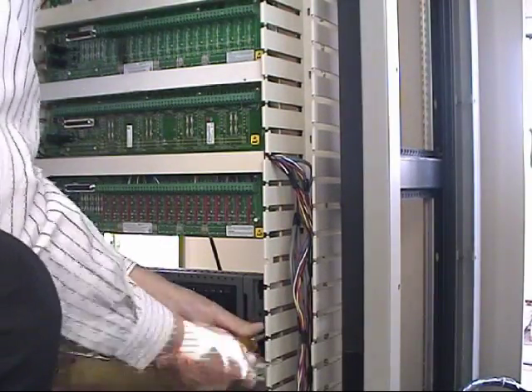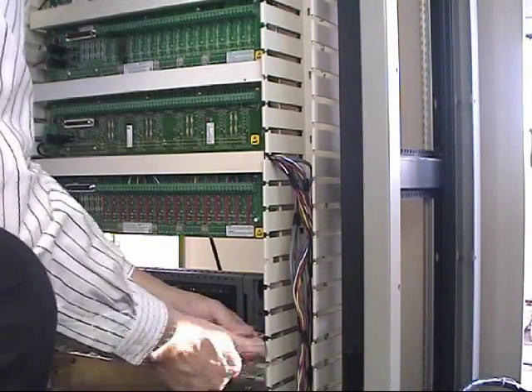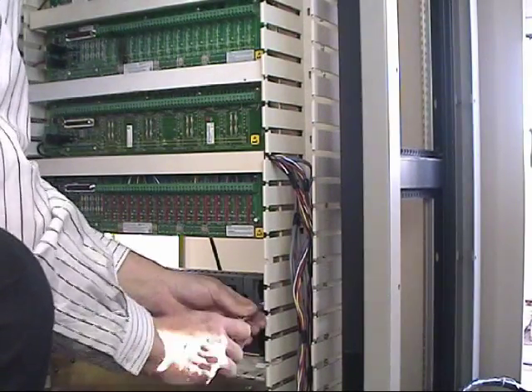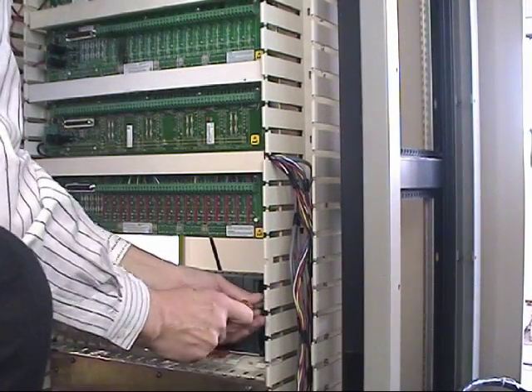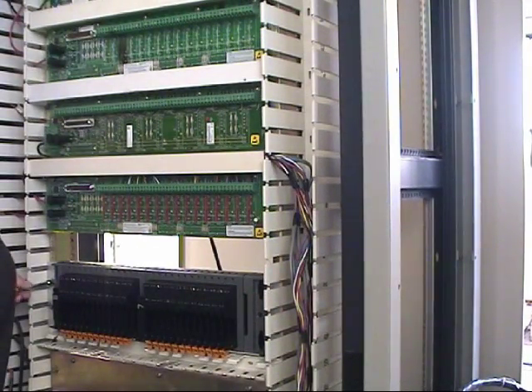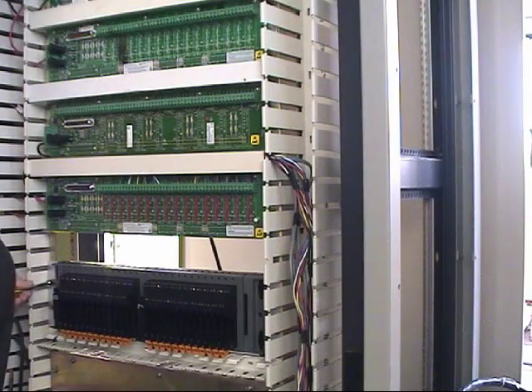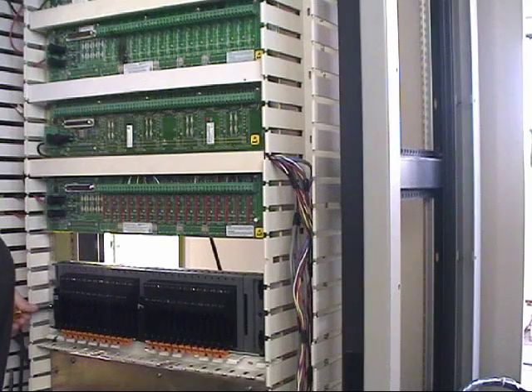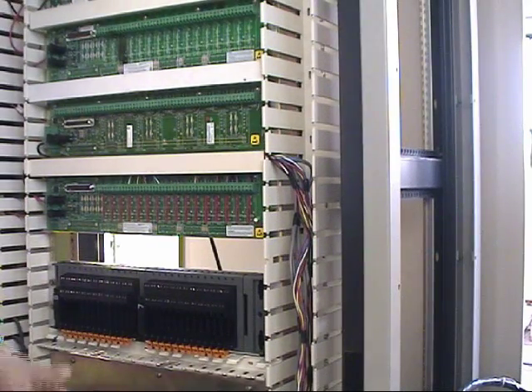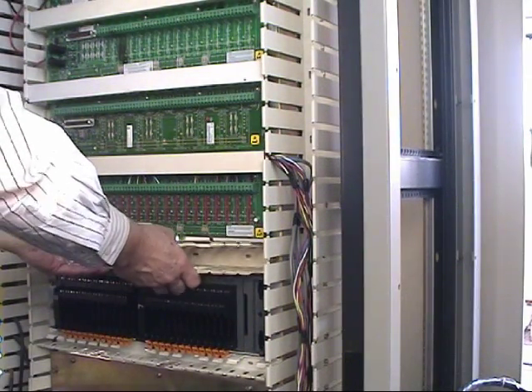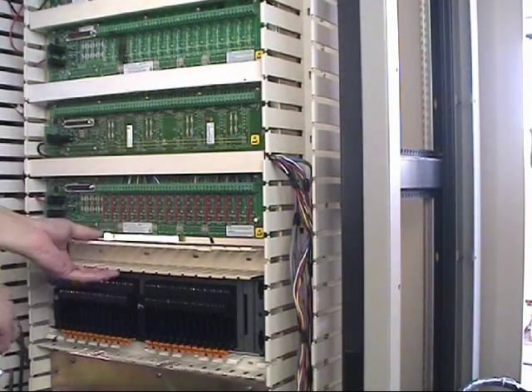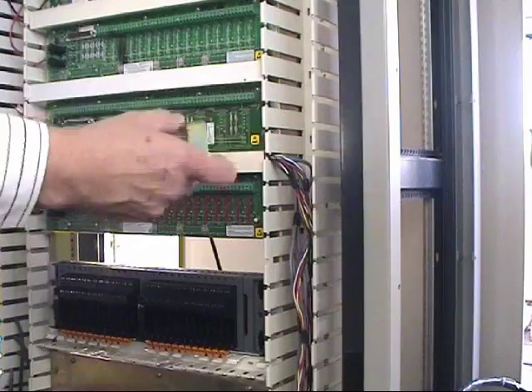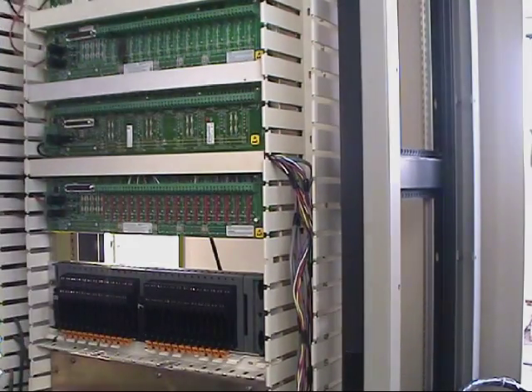We'll secure the CHARMS I.O. rack securely into the cabinet as the first step. Now after doing this, we can either install the upper cable tray at this point or we can elect to do that later to give us easier access into the terminal blocks, and I'm going to elect to do that as a third step.